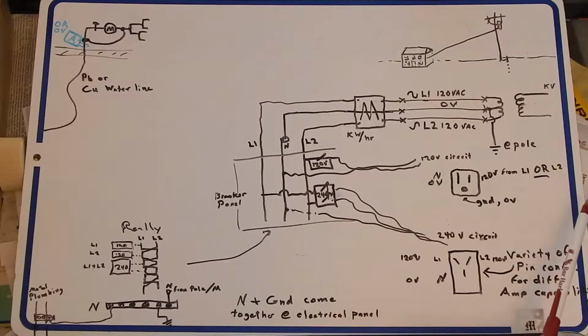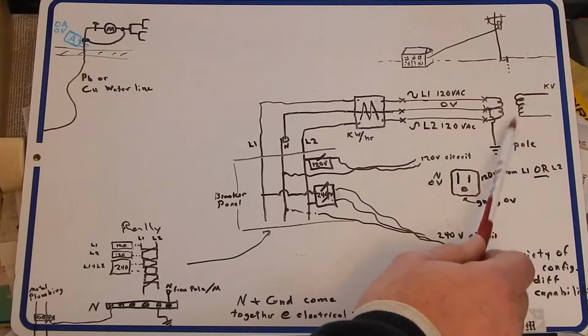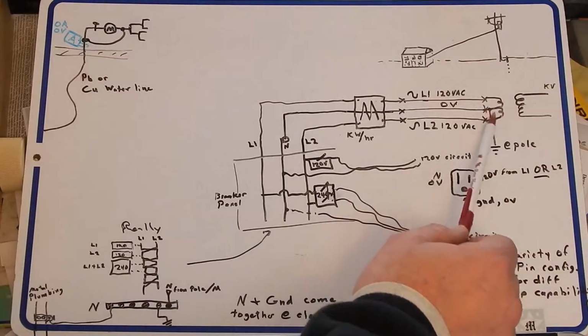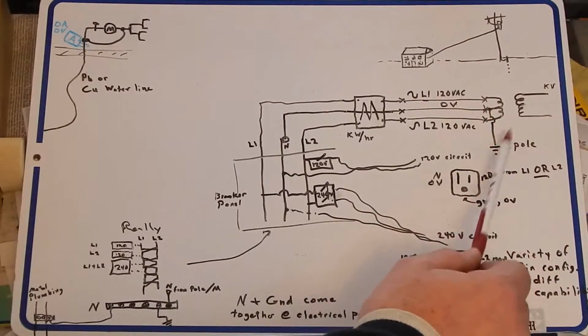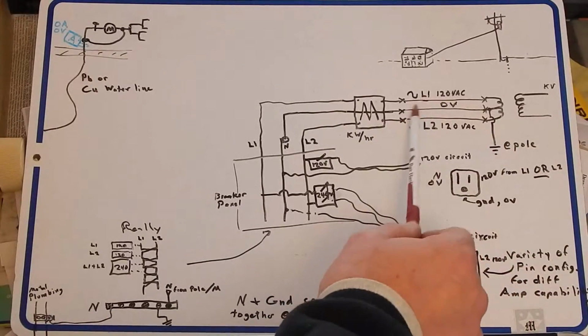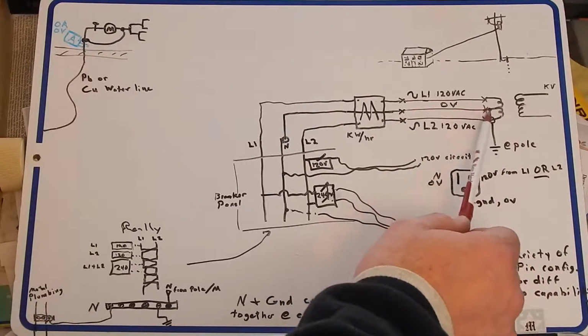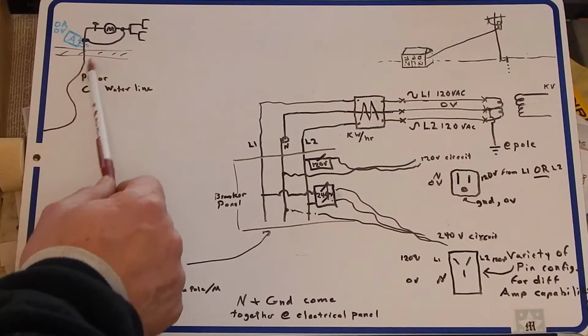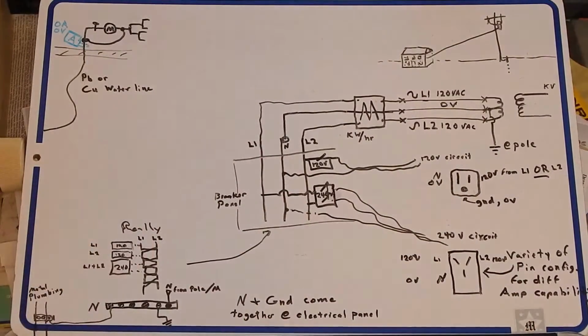The other thing I mentioned is the ground right at the pole, where this neutral is also connected. That's relevant because if this neutral wire is broken, your neutral current is going to go into the earth, and into your water line, and back into your house. That's no way to run a railroad.